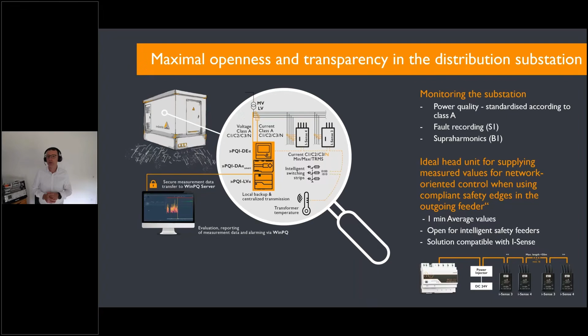With just an insertion of all these protocols I've mentioned, we now have an ideal head unit for supplying measured values for network controlling and the feeder. We can monitor the feeders with our iSense technology, store the data, and transfer it via open protocols like 104 or MQTT to SCADA systems for better control.